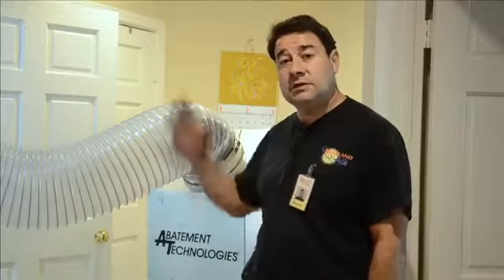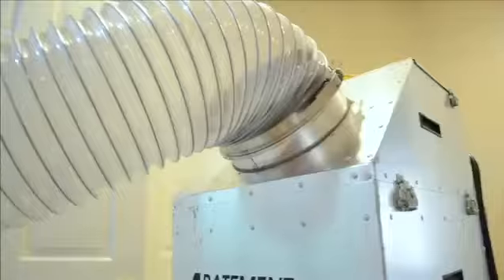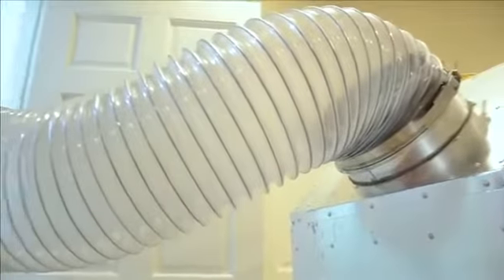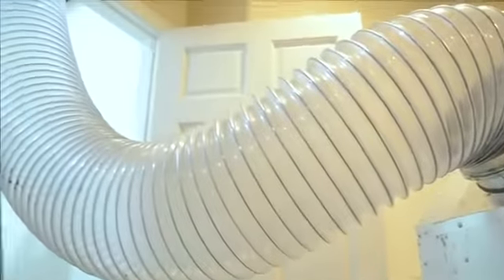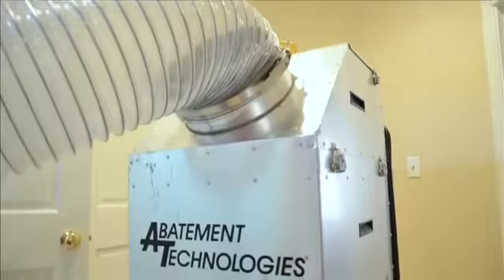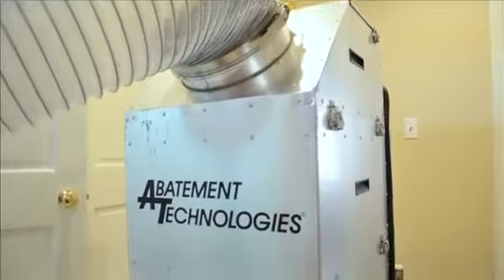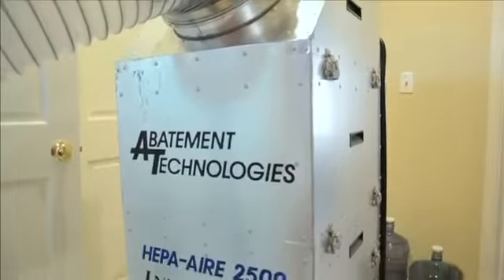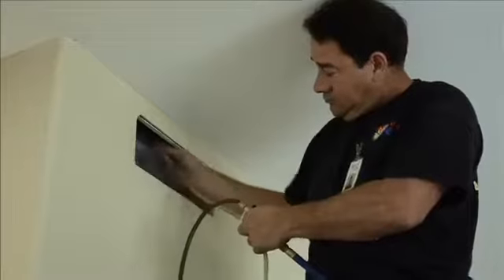Okay, we're going to perform a basic duct cleaning on a home that has a furnace located in the attic. This hose connects directly to the plenum, which is the proper way to do the reverse sweep duct system. We're using the Abatement Technologies HEPA Air 2500 negative air machine with an air wand. We use air pressure through the ducts, brush them, and then use a sanitizer inside the ducts.